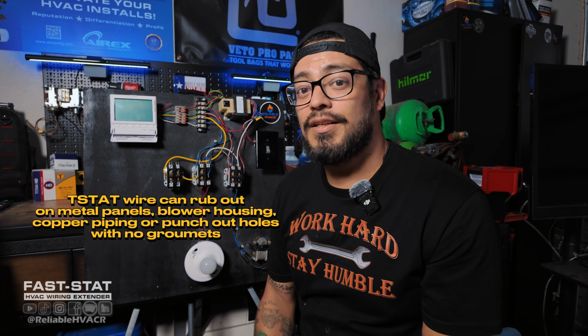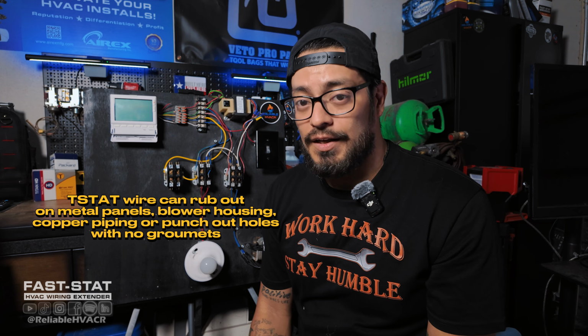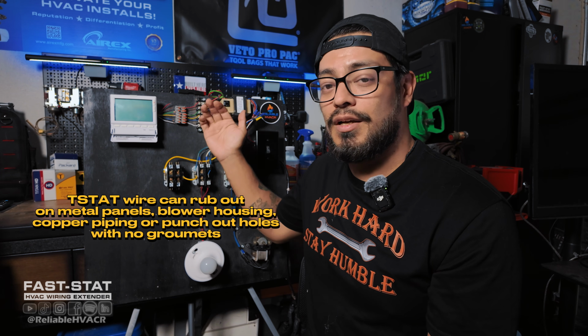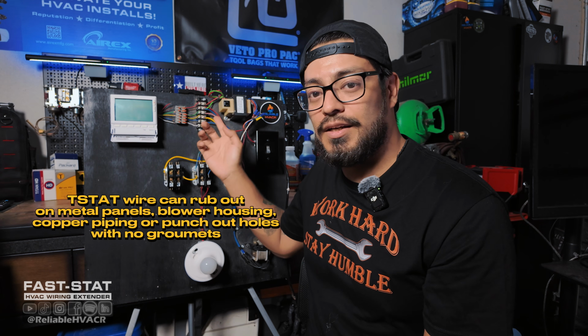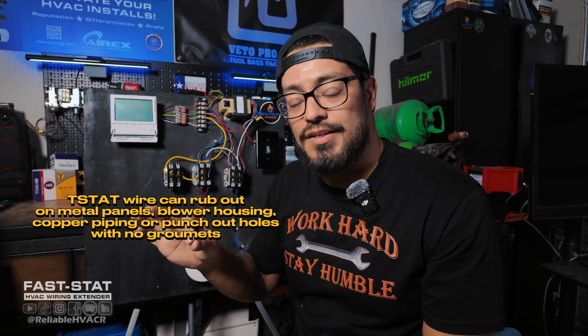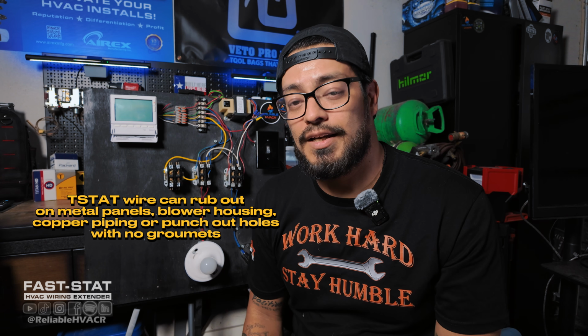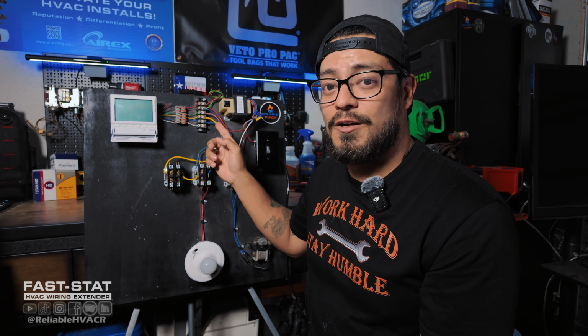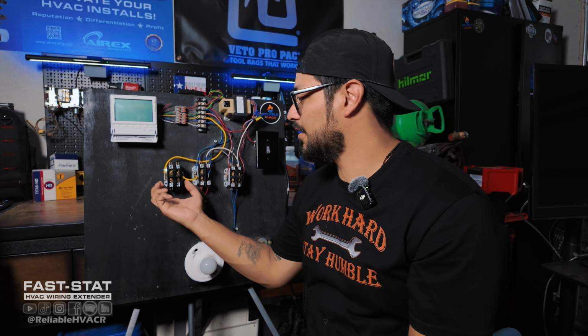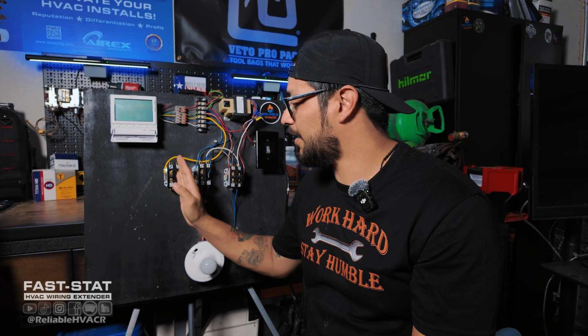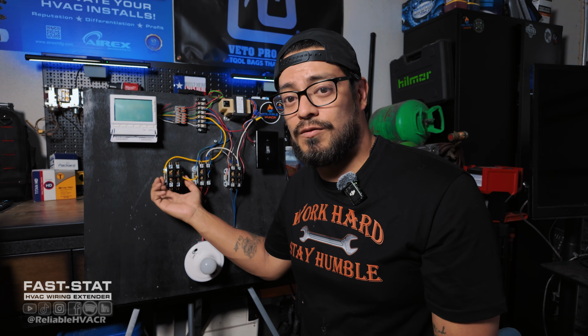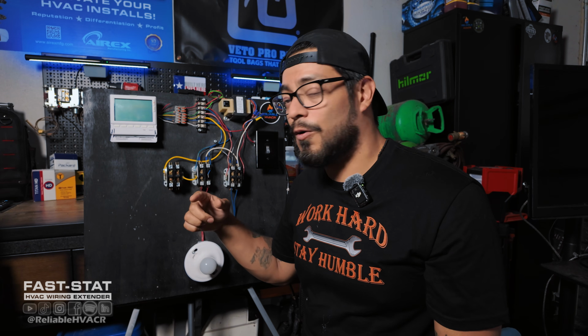If the fan does turn on, the next thing you want to do is set it to cool. And if it trips, then you know you've got a short going to your cooling, either from Y to the board, so check any safeties that it has, or it's going outside and you've got a short going out to your contactor. All that does is send output to either the board or straight out to the contactor. It's going to land on the contactor coils right here, which is low voltage. On these contactors, you've got high voltage on 2 poles, 3 poles, whatever it is that you're working on. And these little side connections on here are the coil, which is 24 volts. All it is doing is making sure that stays either open or closed. Magnetic field, when it energizes, will close those contacts.